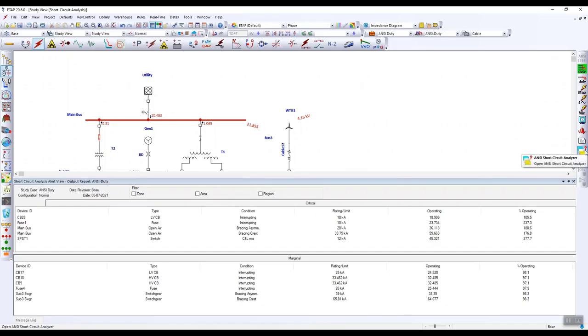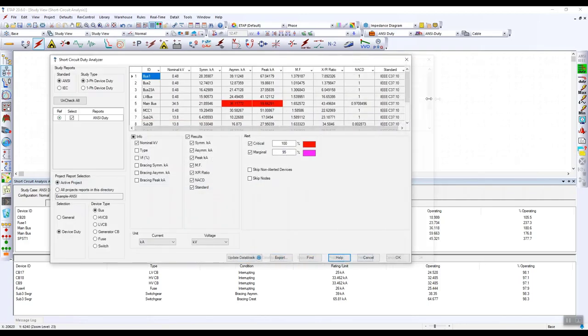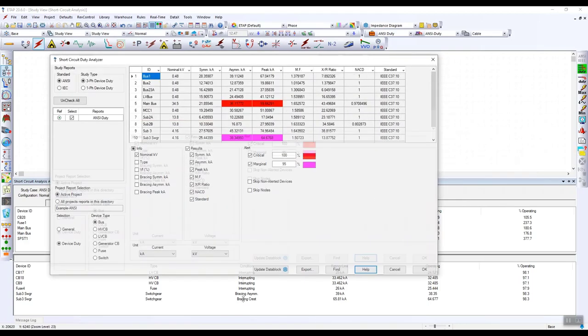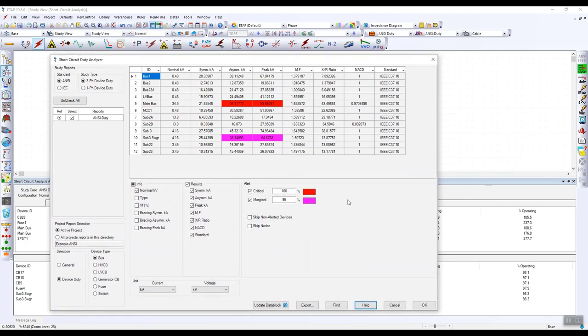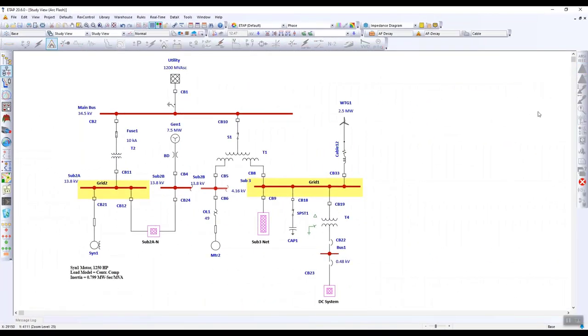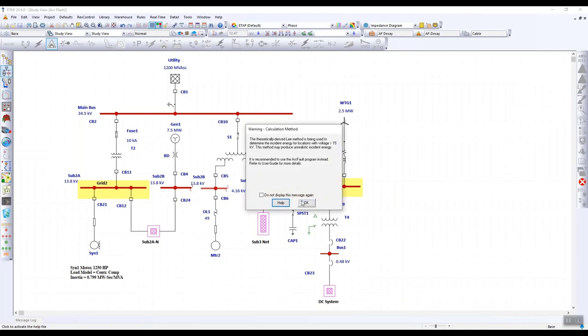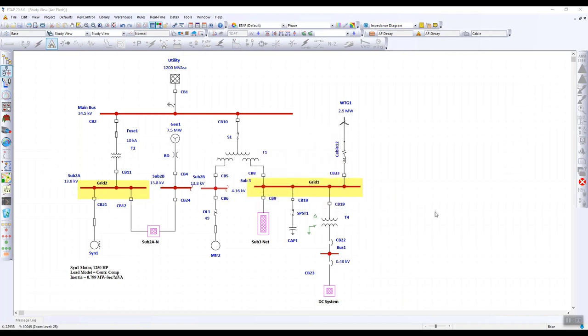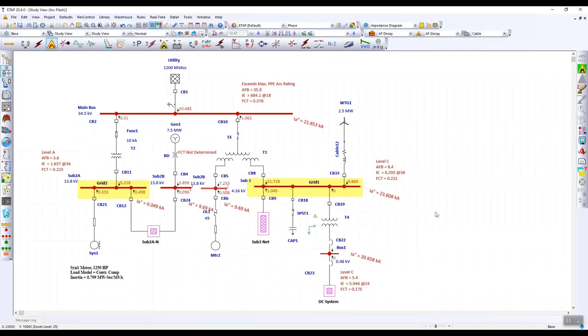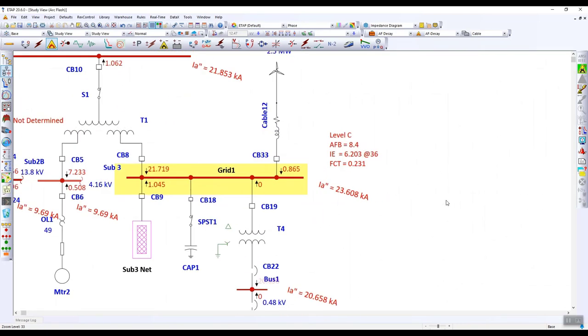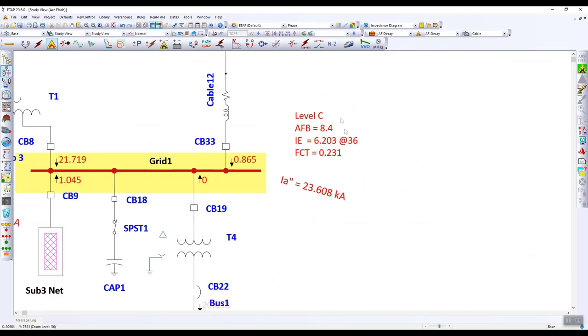We can also see our results in a tabulated view through our analyzer. In this, we can see the output results that were generated during our short circuit study. In here, we can also compare multiple output reports, which will actually come in handy when we're talking about arc flash. Just like load flow and short circuit, once we run the arc flash study, we can see the results populate on the single line diagram. We see the energy level, arc flash boundary, incident energy, and fault clearing time.